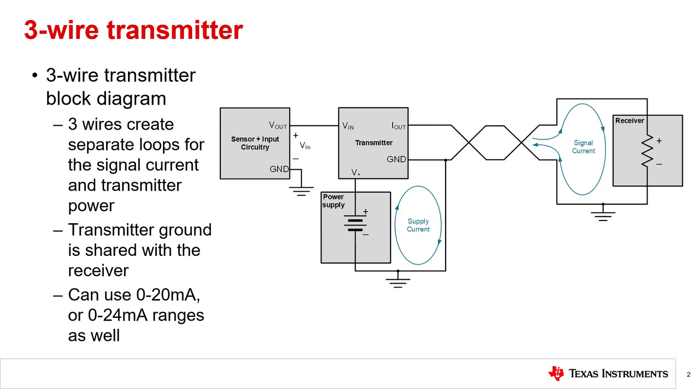In a previous video, we introduced the following characteristics of a 3-wire 4 to 20 milliamp transmitter. A 3-wire transmitter uses two transmission wires to connect the transmitter output to the load and the receiver's ground to the transmitter's ground. Typically, the third wire in this 3-wire transmitter connects the local supply to the device. But there are applications where the transmitter uses the same supply as the receiver.